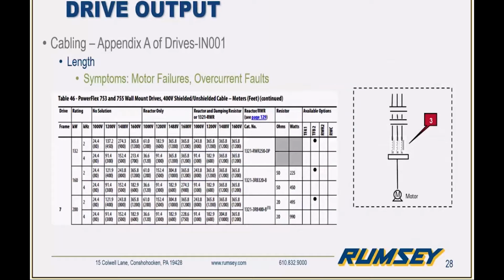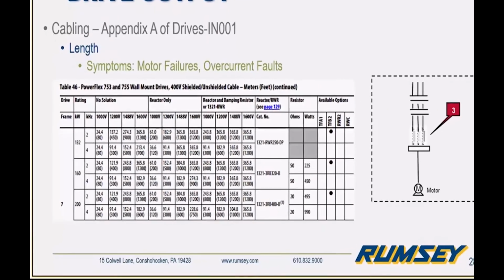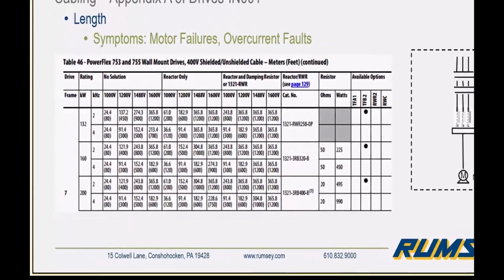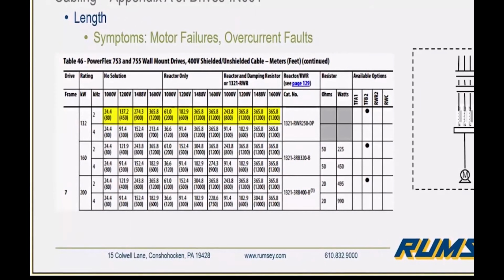Okay, so moving on to the output of the drive. One of the most common field-related issues are due to the motor cable lengths themselves, and what we see commonly are motor failures or overcurrent faults. In the drive's wiring and grounding guidelines, the drive's IN001, there's actually tables available for your specific drive that show the maximum allowable lead length for that motor, or between the drive and the motor, basically.